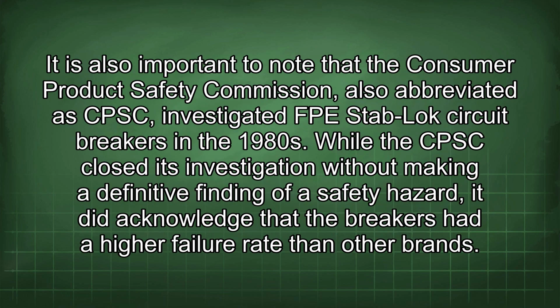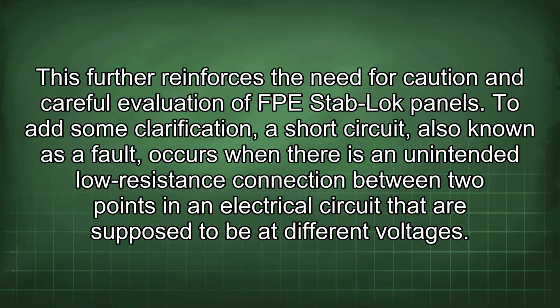It is also important to note that the Consumer Product Safety Commission, also abbreviated as CPSC, investigated FPE Stab-Lok circuit breakers in the 1980s. While the CPSC closed its investigation without making a definitive finding of a safety hazard, it did acknowledge that the breakers had a higher failure rate than other brands. This further reinforces the need for caution and careful evaluation of FPE Stab-Lok panels.